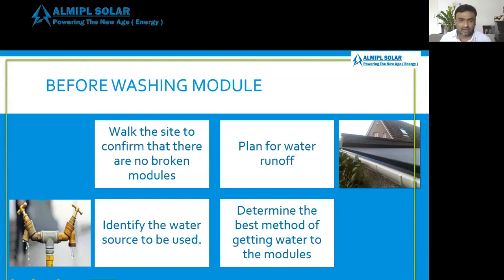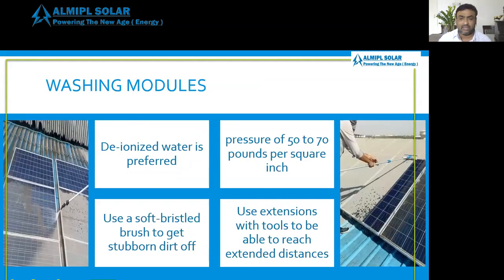Plan for water runoff. Identify the water source to be used. Determine the best way of getting water to the modules. When washing modules, deionized water is preferred. Prefer a pressure of 50 to 70 pounds per square inch. Use a soft bristle brush to get stubborn dirt off. Use an extension tool to reach extended distances. So we need to take care of all these things.